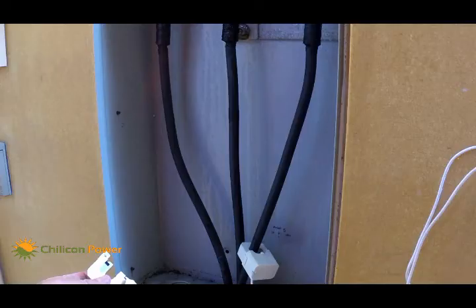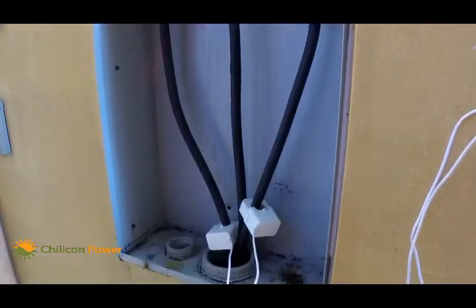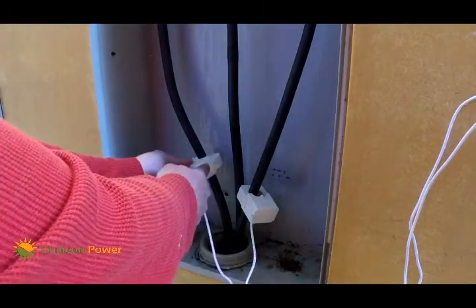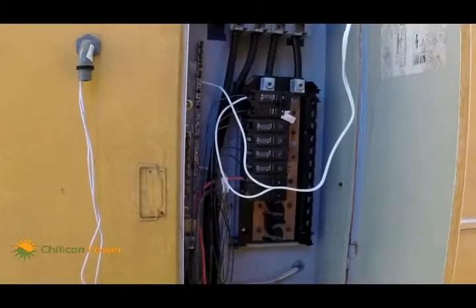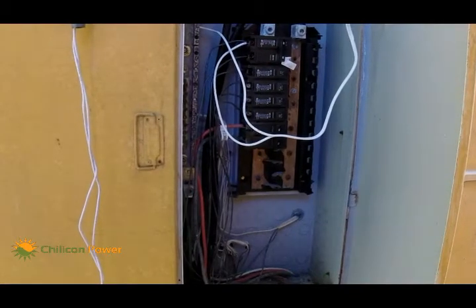Welcome to the home energy meter video. This is a home energy meter in the upper right-hand corner, wired into the utility box opening where the utility connections are made. You can see clamps are applied, and these clamps should be placed in opposition to one another so that one can detect the current on opposite phases. You can use the clamps themselves to see that they're in opposite locations. This is the voltage sense line going into the clamp — you can see it's wired into a breaker and into neutral.